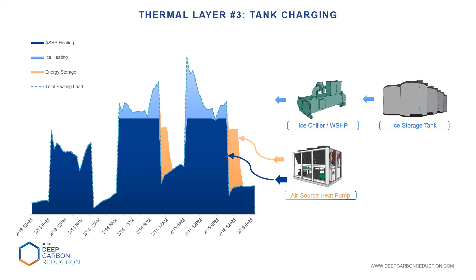One interesting thing brought up in the video, but maybe not obvious, is that once you've depleted your thermal battery, there is a way to recharge it using your actual air source heat pump. The orange area shown is the air source heat pump operating to effectively melt the ice tank, recharging that thermal battery, and you can do that in the off hours. So this system is all about shifting load, similar to cooling, but now in a heating application where you shift load from daytime to nighttime.